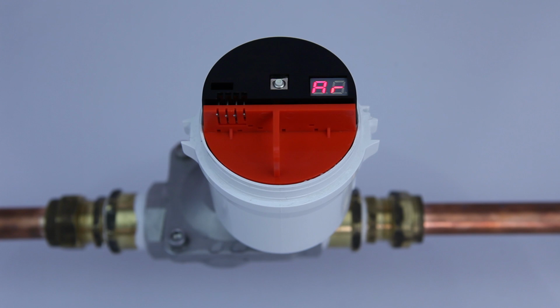Auto reset. The auto reset function only appears if the exclusion period is turned on. This function is designed for public washrooms, and it allows the AquaTrip to automatically turn the water back on if it has been previously tripped. While the exclusion period is active, all water use is ignored. Outside of the exclusion period, if a leak is detected, the water will shut off. However, if automatic reset is turned on, when the next exclusion period begins, even if the leak is still present, the water will automatically be turned back on again so the facility can be used, even with the leak still present.